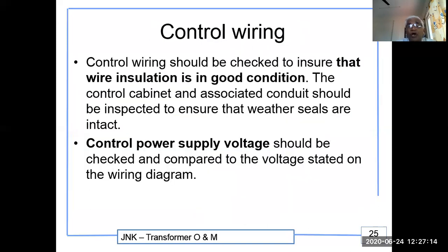Control wiring. Control wiring should be checked to ensure that wire insulation is in good condition. The control cabinet and associated conduit should be inspected to ensure that weather seals are intact. Control power supply voltage should be checked and compared to the voltage stated on the wiring diagrams.